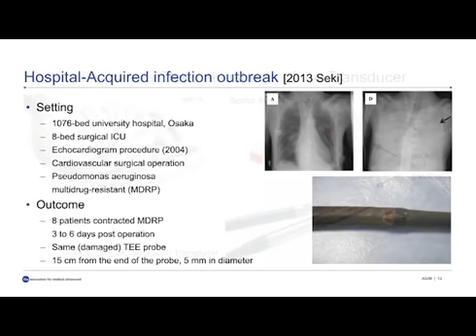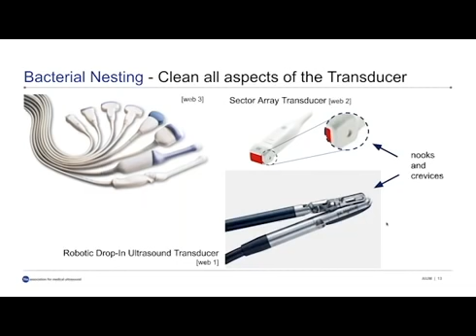And it does entail cleaning ultrasound gel out of these nooks and crevices that are highlighted here on this phased array probe on the side, where maybe a needle guide or some other 3D guide can be attached. And these nooks and crevices allow ultrasound gel to stay longer, even if you just wipe superficially with a disinfecting towel. If you don't get all the ultrasound gel out, then you can have transmission here. And with this robotic drop-in ultrasound transducer on the bottom, you can see very well that if you don't rinse it under flowing water, it will be next to impossible to get all the gel out.